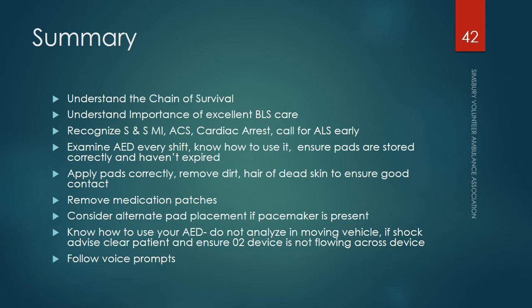Following the voice prompts, that's the best way to ensure that you're using the AED correctly. And if the voice prompts don't occur once you place the pads on, troubleshoot. Make sure you've turned on the machine. Make sure that you've attached the electrodes. If you're checking the AED every shift and it reads okay, it should work correctly. And again, think about human error and go back through your steps again and see what it is you've done right or wrong and what you need to do to correct the problem.